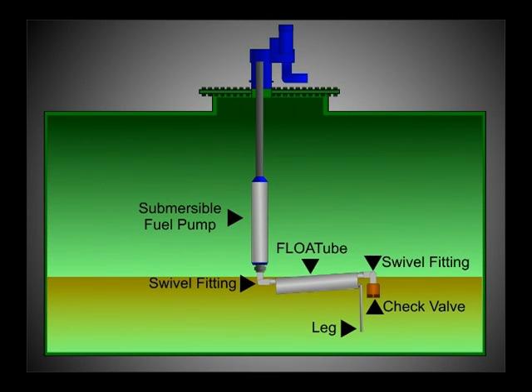Anatomy of a float tube. The float tube can be attached to the end of a submersible pump and fits through a four-inch riser. In this diagram, you can see the float tube is connected to a submersible fuel pump along with two swivel fittings, a check valve, and a leg.